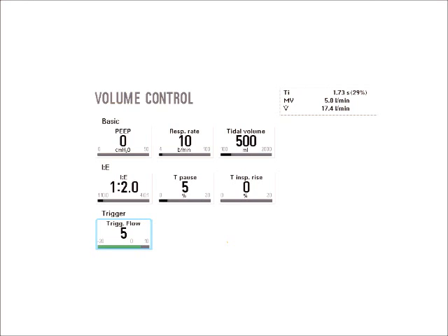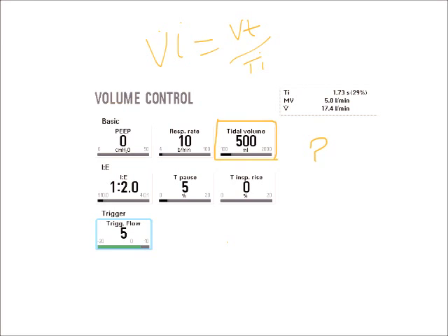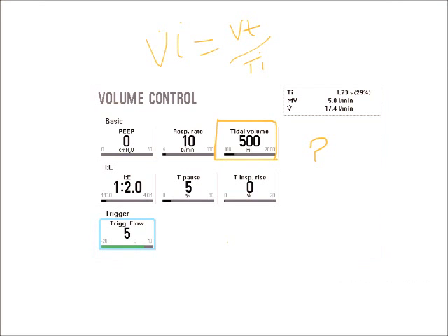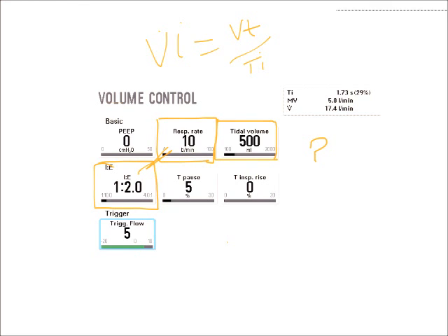As I stated before, the components for flow are my tidal volume and my inspiratory time. I do have a tidal volume setting; however, there is no setting for inspiratory time. However, there is a setting for my IE ratio and a respiratory rate, and both of these will affect my inspiratory time.